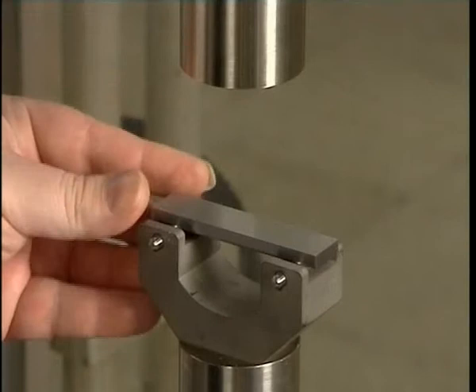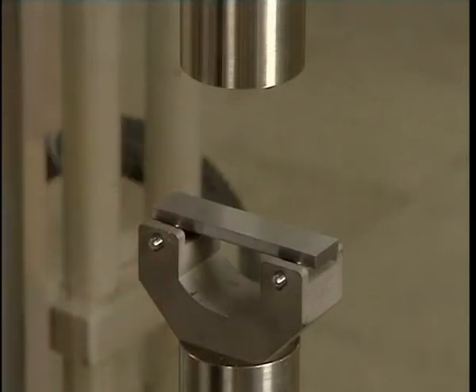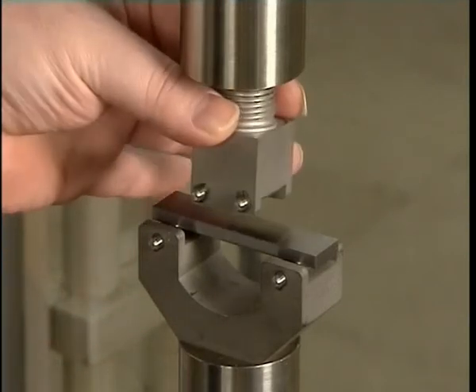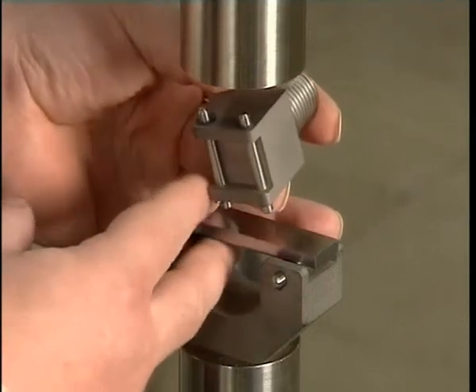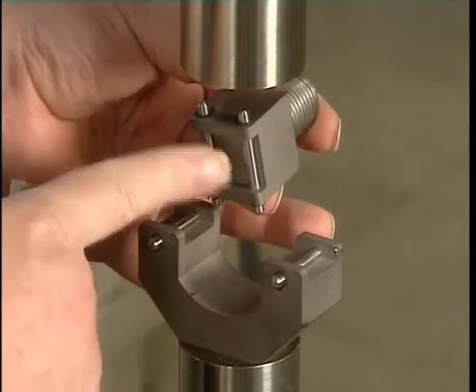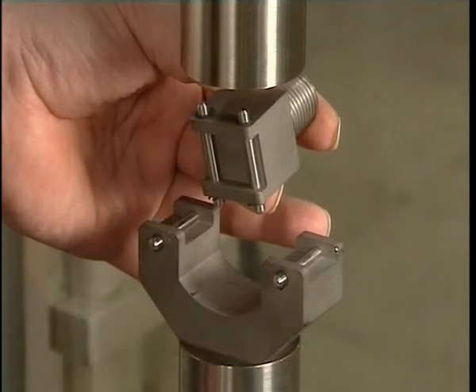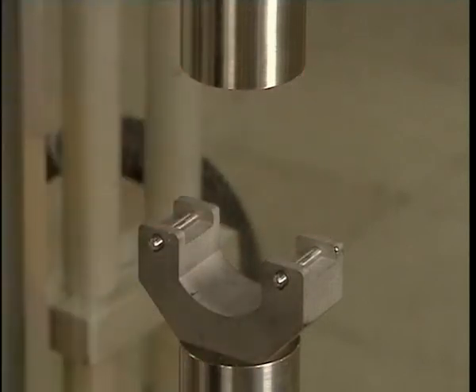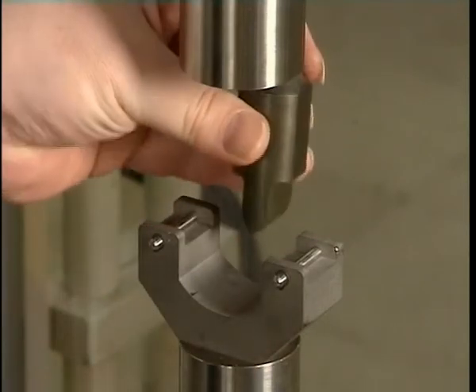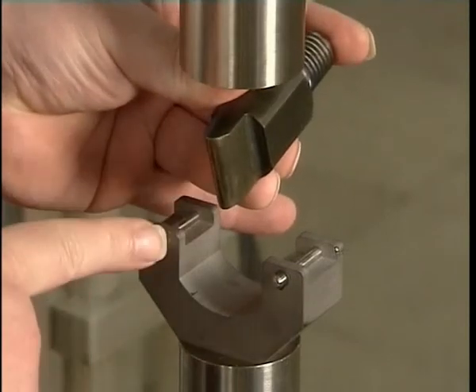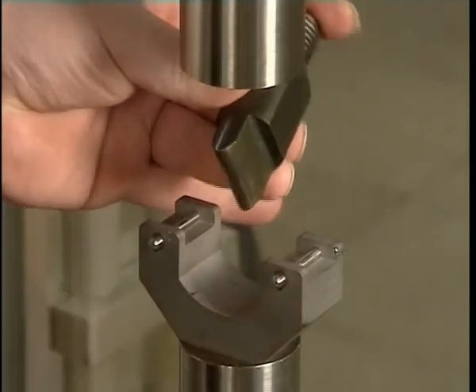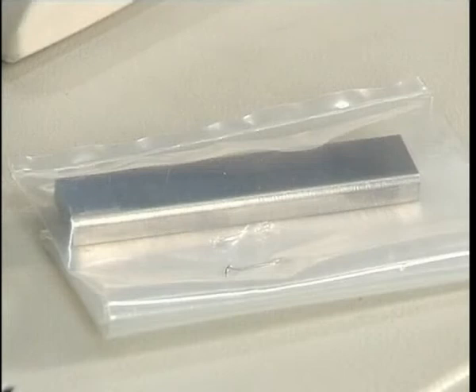This machine is set up for the bend testing of metals, either 4-point bend, 1, 2, 3, 4, or in this case I have to do a 3-point bend test, 1, 2, 3. This test piece has been machined to size for bend testing and sealed into a plastic bag to protect it.